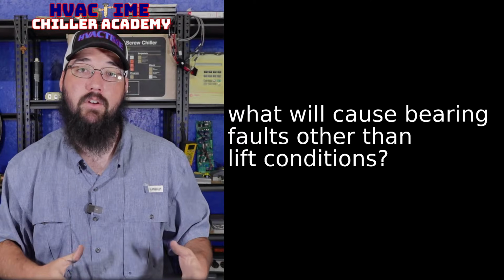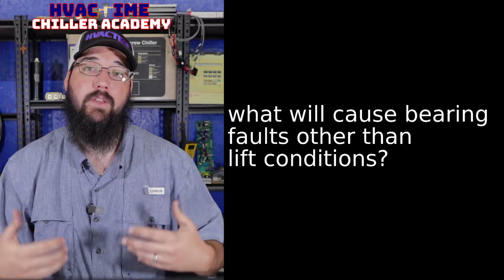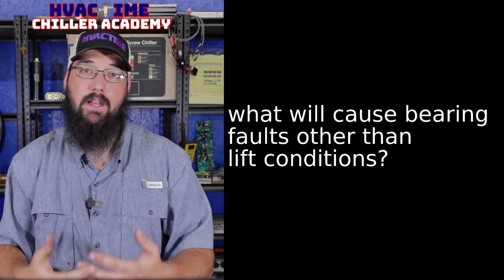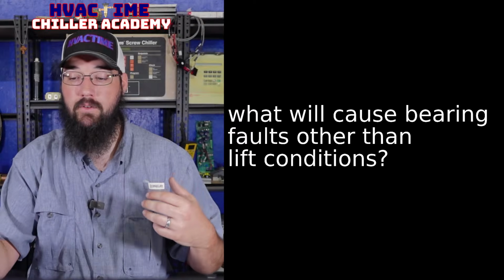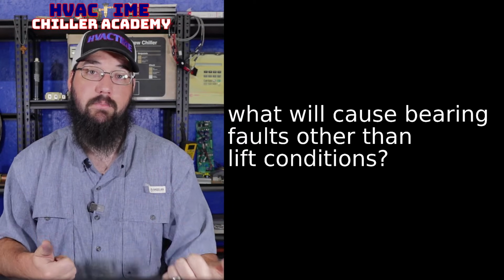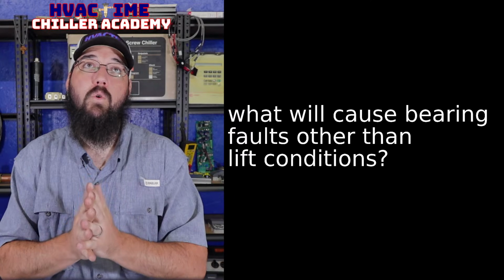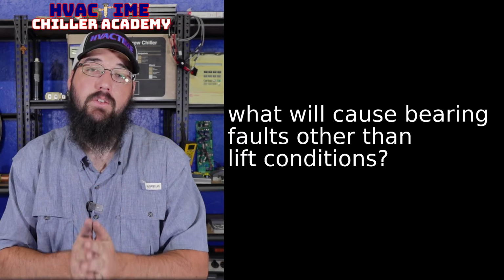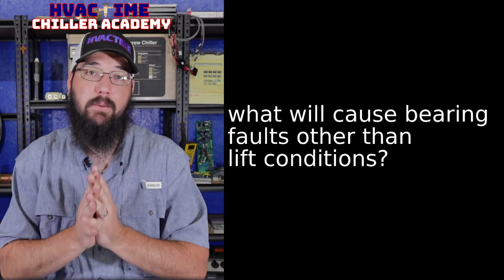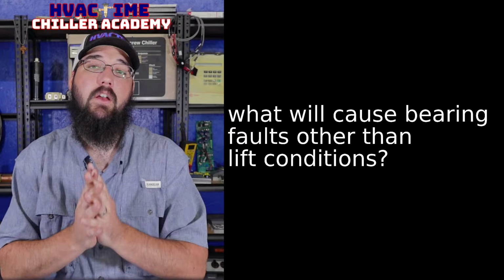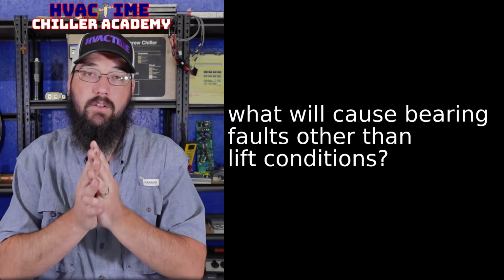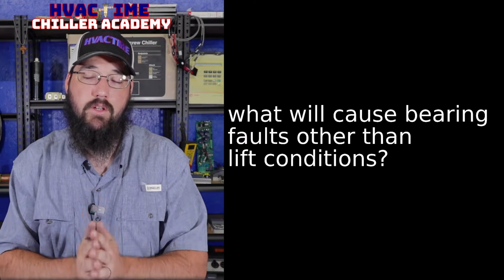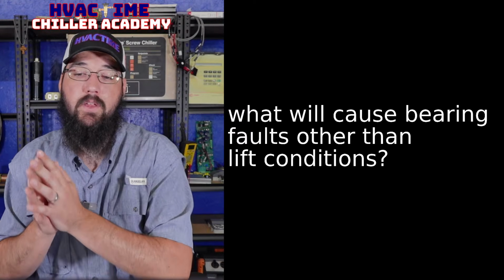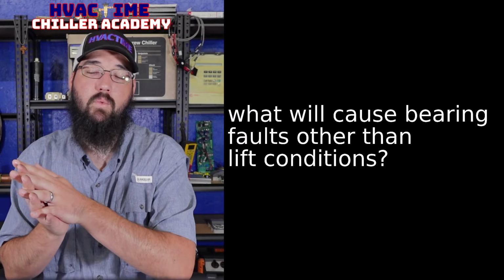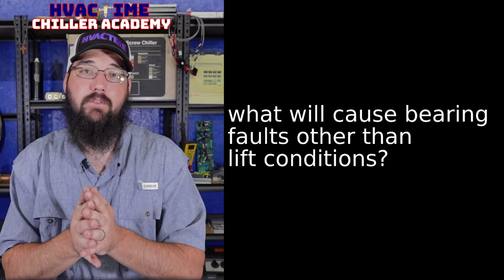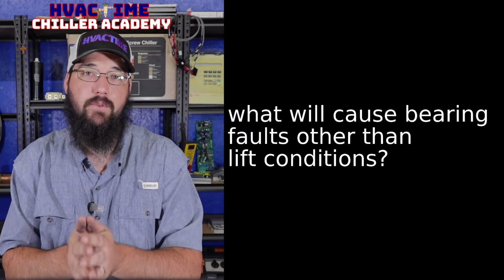Let's go ahead, change this inverter out. Let's see how it performs with a known good inverter. And if we're still having bearing issues, then it could be either the shaft, it could be some residual issue with the bearings themselves, or it could be the calibration. So there's a very specific process to doing a bearing calibration and saving it correctly on these compressors. And it has to be done just right. If you don't do it just right and there is an issue, then that bearing calibration will completely wreck your ability to safely get that compressor to operate. It's just not going to do it.